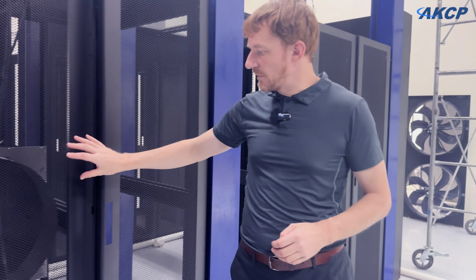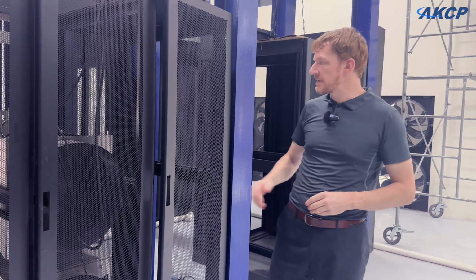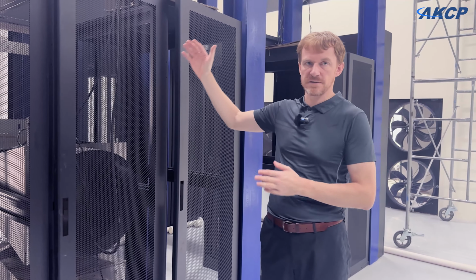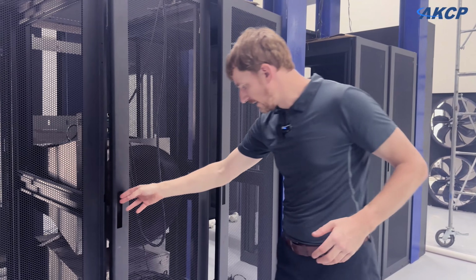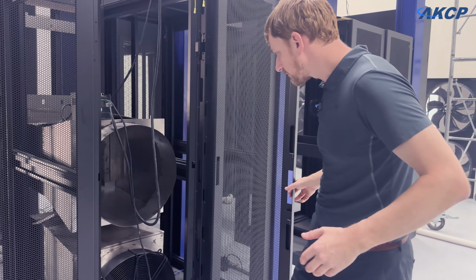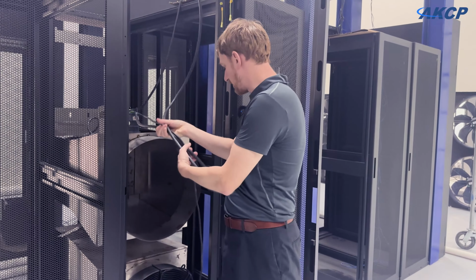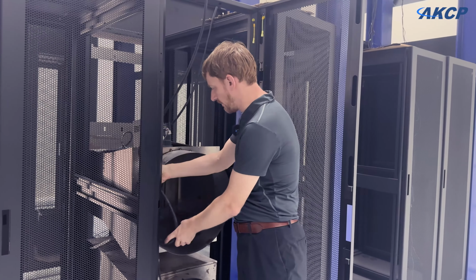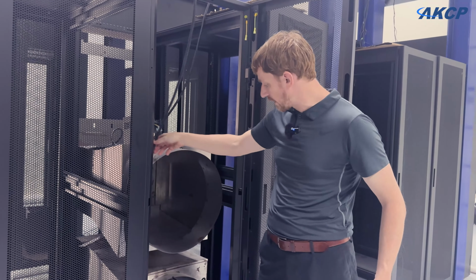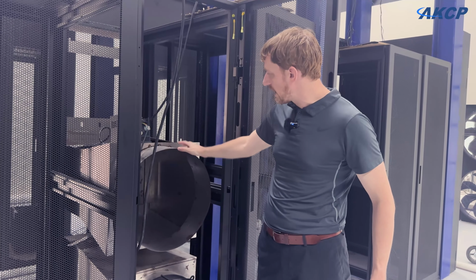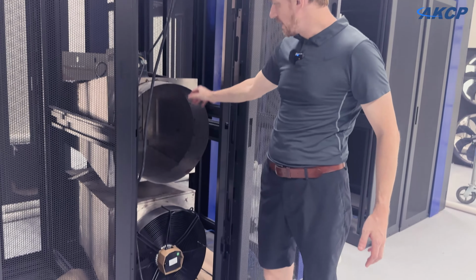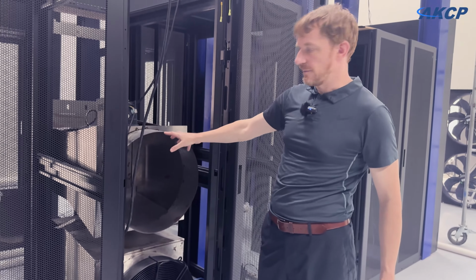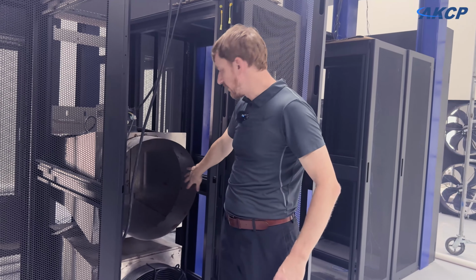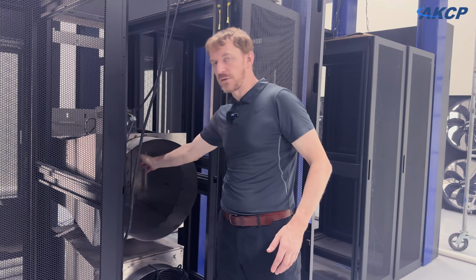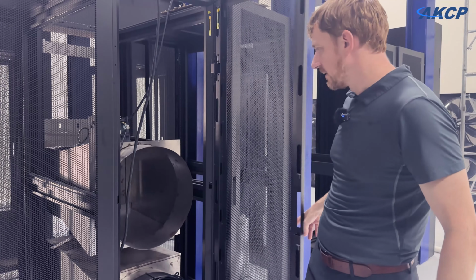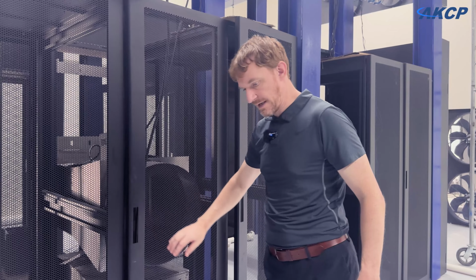Inside the actual racks, we're not putting servers, we're putting space heaters. We have 9 kilowatt space heaters, 3 of them giving us 27 kilowatts per rack, and we can see on this one how it's going to be set up. We've just been testing one here to make sure that as we had the power connected, the bus bars and everything were all working. This one isn't populated yet, but basically we have the fan on here, and on the other side of that is the heater. We're making sure all the air is funneled through that heater, avoiding bypass air, so we can maximize our air usage and cooling in here.